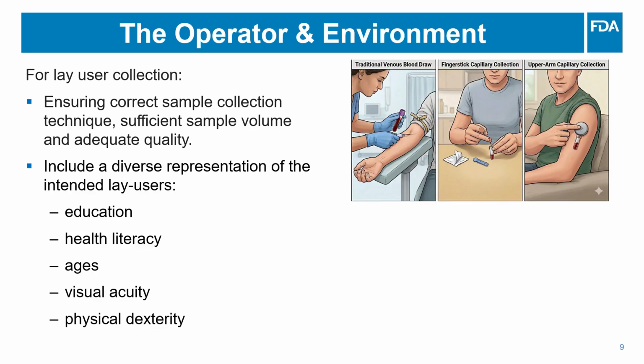The red blood cells in a capillary sample are highly susceptible to hemolysis. This is often caused by the mechanical stress of squeezing the tissue to force the blood out, or by the shear force of the blood being pulled through a tiny microneedle or a vacuum channel. It will be very important to demonstrate that lay users can collect a sample that is of sufficient volume and quality. Studies should include a diverse representation of the intended lay users. This means accounting for different levels of education, health literacy, ages, visual acuity, and physical dexterity. Users should be able to do the sample collection process without any coaching or prompting to represent real use of the device.